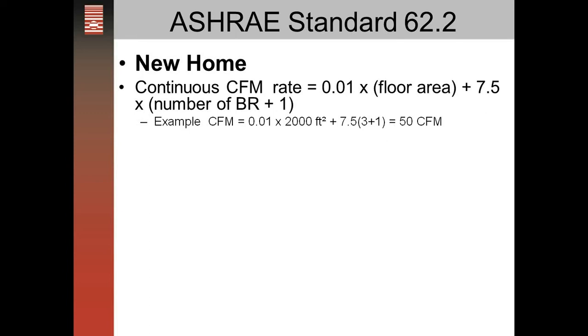An example of that is if you had a 2,000 square foot home: .01 times 2,000 plus 7.5 times 3 plus one — the number of bedrooms plus one — and it comes up with 50 CFM.